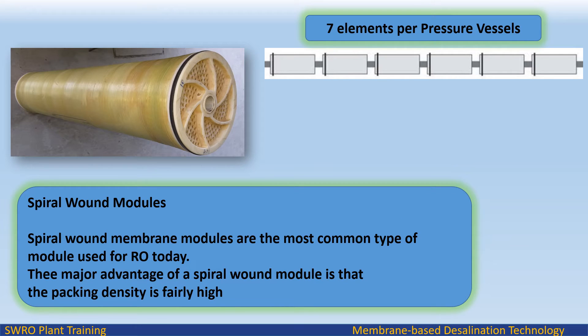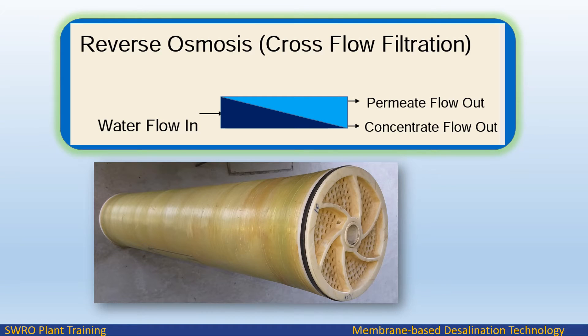Spiral wound membrane modules are the most common type of module used for RO today. The major advantage of a spiral wound module is that the packing density is fairly high. In crossflow filtration, feed water passes tangentially over the membrane surface rather than perpendicularly to it. Water and some dissolved solids pass through the membrane, while the majority of dissolved solids and some water do not pass through. Crossflow helps to minimize fouling or scaling of the RO membrane.